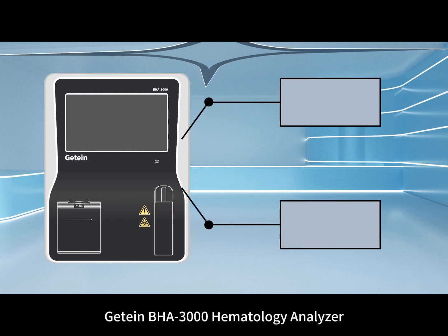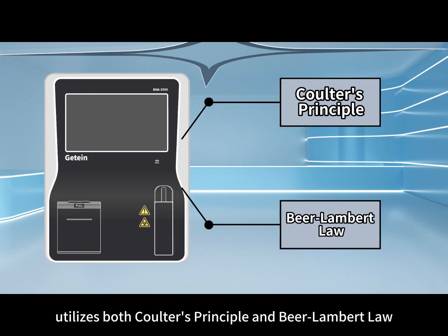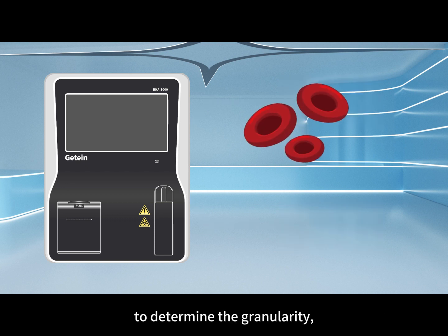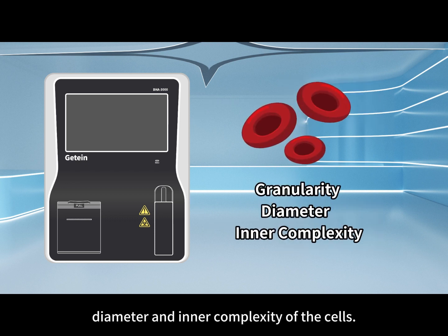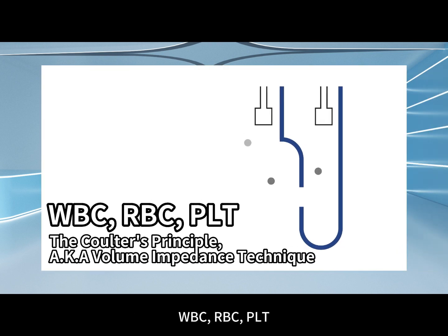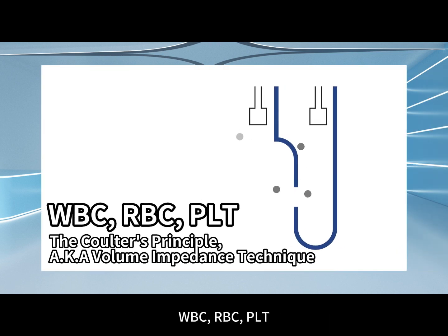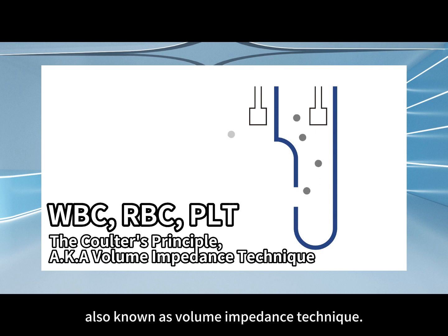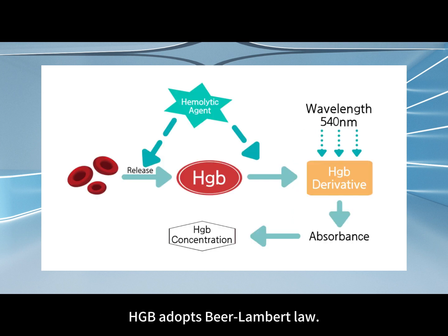The BHA 3000 Hematology Analyzer utilizes both Coulter's Principle and Beer-Lambert Law to determine the granularity, diameter, and inner complexity of the cells. WBC, RBC, and PLT adopt Coulter's Principle, also known as the Volume Impedance Technique. HGB adopts Beer-Lambert Law.